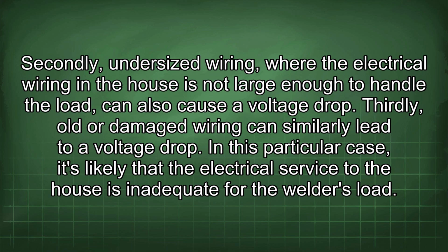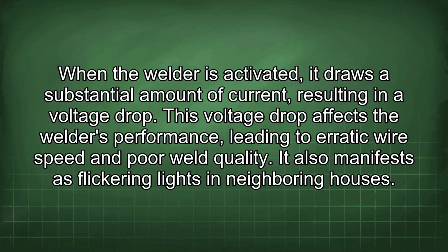In this particular case, it's likely that the electrical service to the house is inadequate for the welder's load. When the welder is activated, it draws a substantial amount of current, resulting in a voltage drop. This voltage drop affects the welder's performance, leading to erratic wire speed and poor weld quality. It also manifests as flickering lights in neighboring houses.